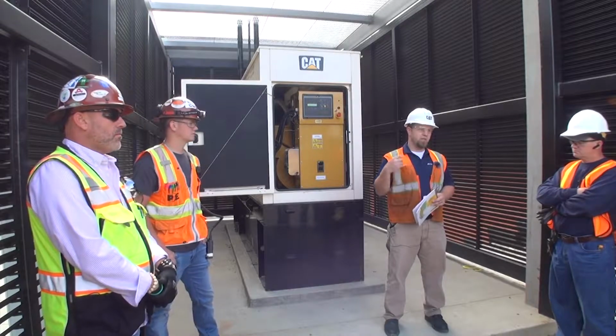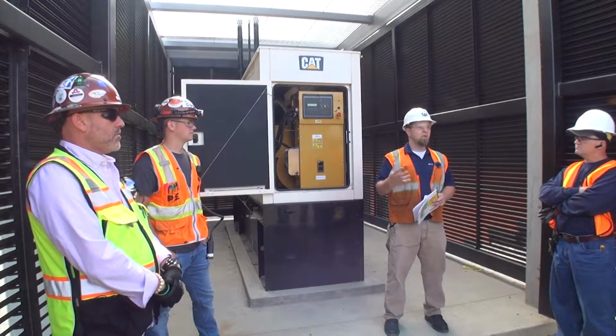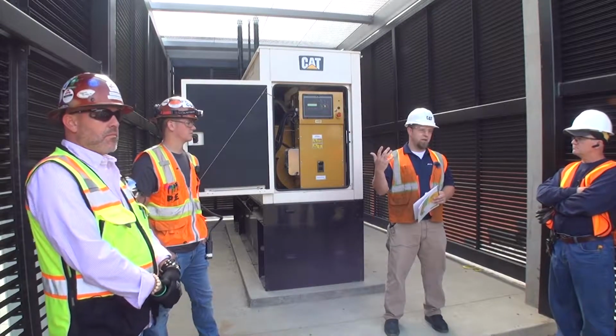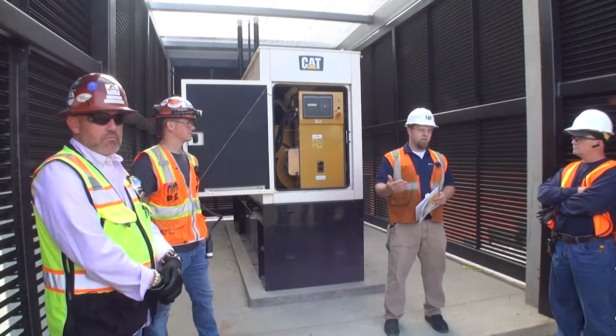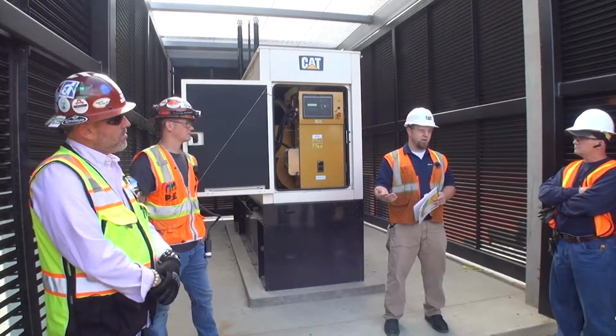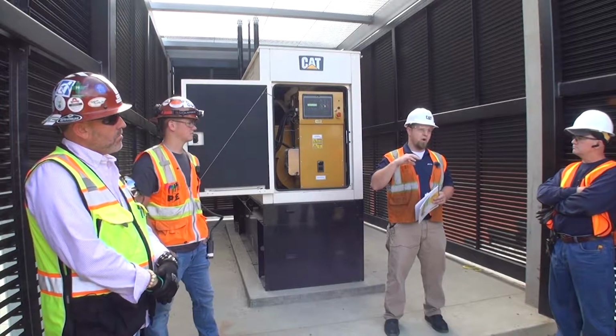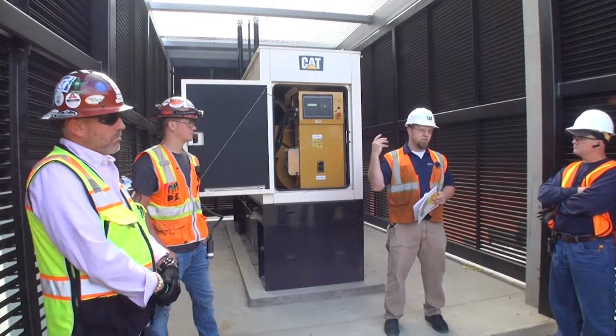The second portion of it is that you need to be doing a weekly walk around. We'll show what a weekly looks like here, and then once a month you need to be doing an actual building transfer — transferring load over from the main source onto the generator.